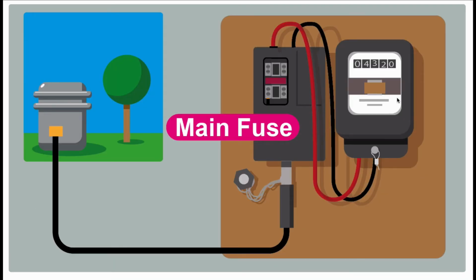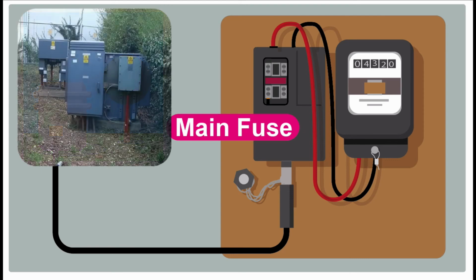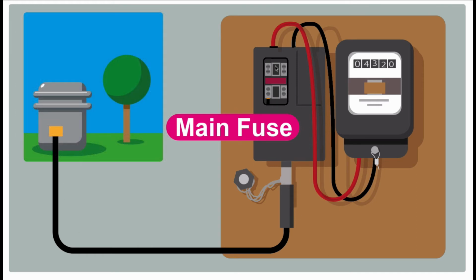Right, the main fuse. We're not allowed to pull this, the service fuse. This is the DNO's equipment and they don't like us to interfere with their equipment. And as you can see, there's nothing between the transformer and this connection here. That goes straight out the house, down the street and into the transformer. So there's nothing between you and the transformer. And if there's a fault here, you're going to get a massive fault current. So we don't want to be interfering with this area whatsoever. And this fuse might have been in place for the last 40, 50, 60 years. Could have been there for ages.